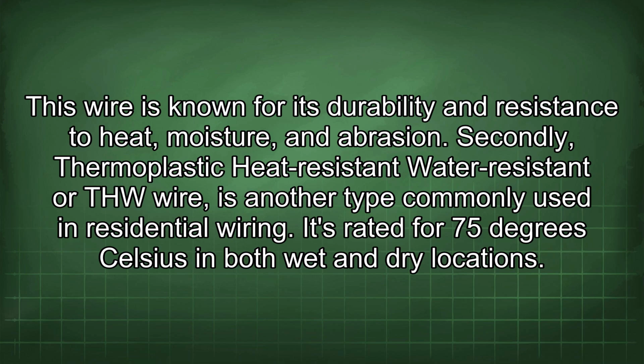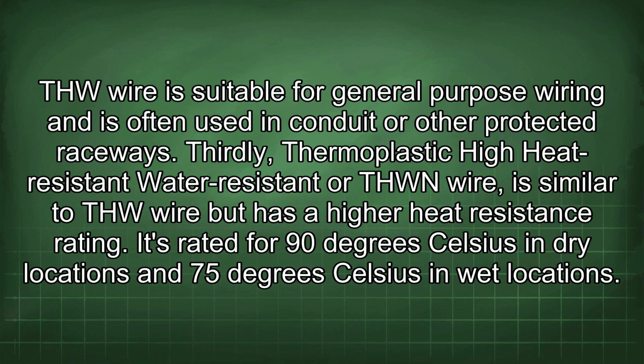Secondly, thermoplastic heat-resistant, water-resistant, or THW, wire is another type commonly used in residential wiring. It's rated for 75 degrees Celsius in both wet and dry locations. THW wire is suitable for general-purpose wiring and is often used in conduit or other protected raceways.